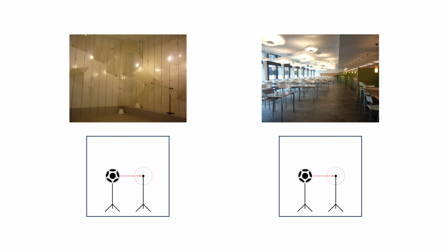The near-source measurement in the calibration room will be referred to as the second step, as in this being the second step of the calibration. The near-source measurement on-site will be referred to as the in-situ correction.